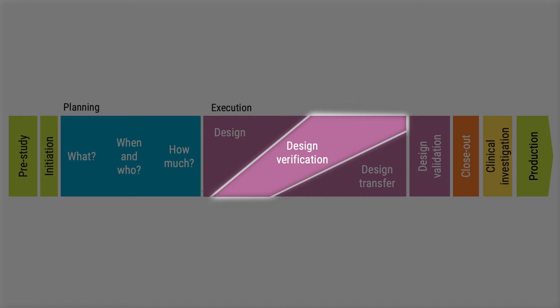We should design the device based on the design inputs defined in the planning phase. When the product has been designed, you need to show that what you did met the design inputs — this is design verification, providing objective evidence that your design outputs meet the design inputs. You may perform design verification on early prototypes, but beware: there is a risk that production products will differ from early prototypes. In fact, early prototypes from engineering often perform better because your best engineers built and tweaked them until they worked as they should.